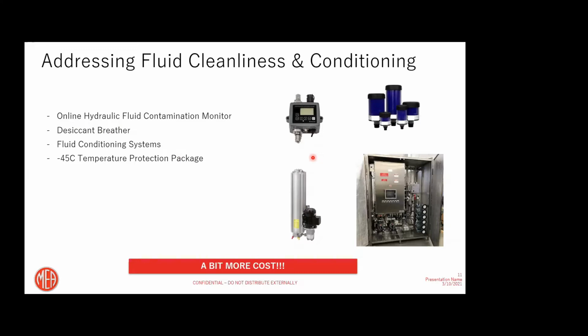So you don't need to run sample tests and so on. You now have very advanced desiccant filters which you install on the reservoir, which really improve the quality of air and any debris coming into the reservoir. You can add a fluid conditioning system for cooling and additional filtration, which is also great. Additionally, you can install a negative 45C temperature protection package, which basically protects your unit and fluid from all the temperature effects. So yes, we can improve the cleanliness and conditioning of the unit, and it will definitely improve the reliability. But again, it's more cost and more complexity and more items to maintain.